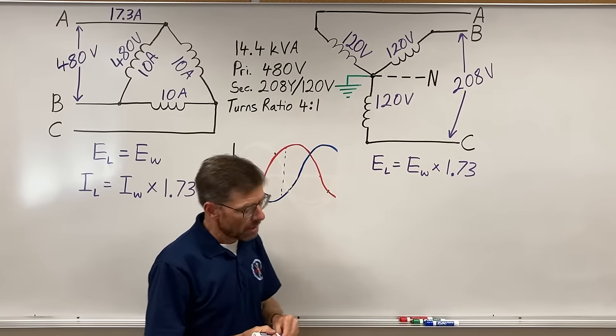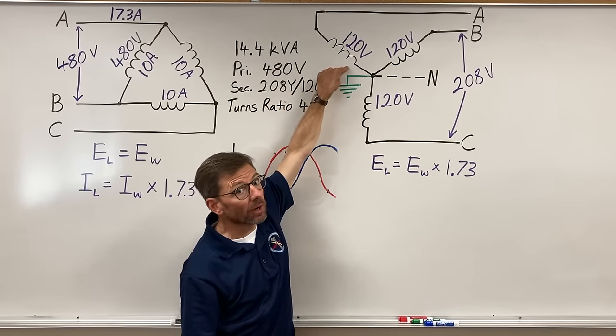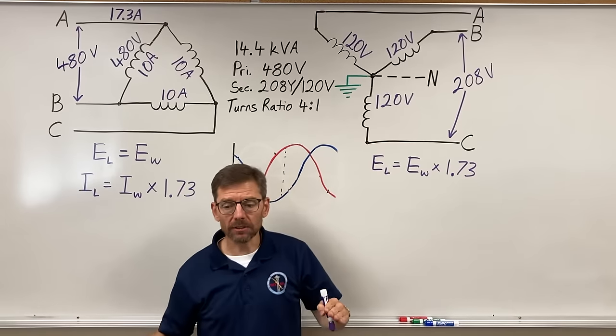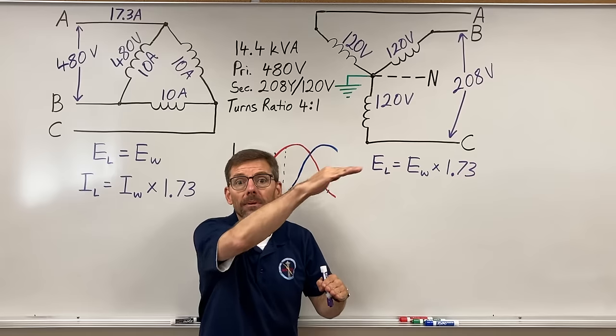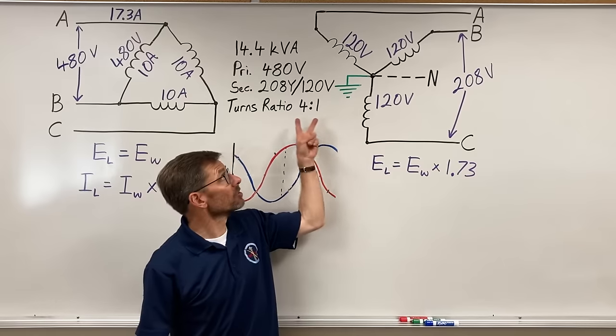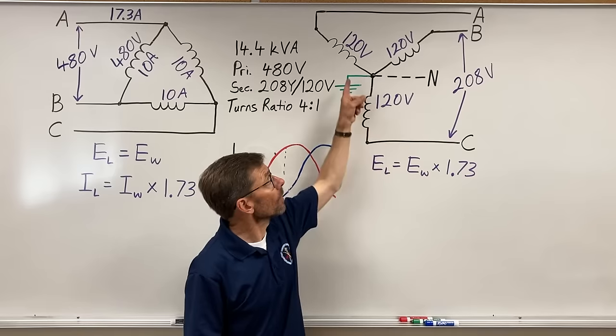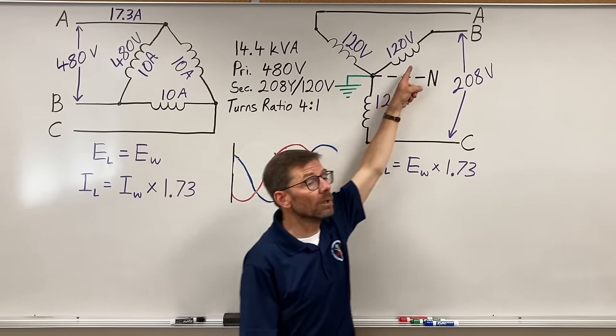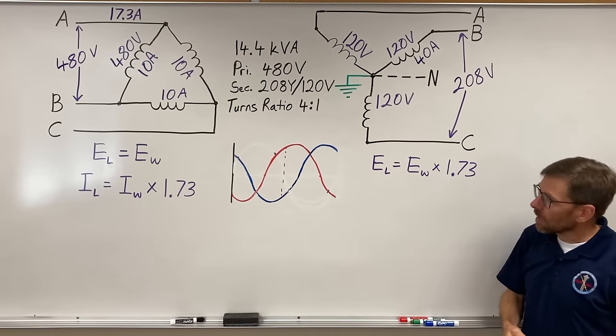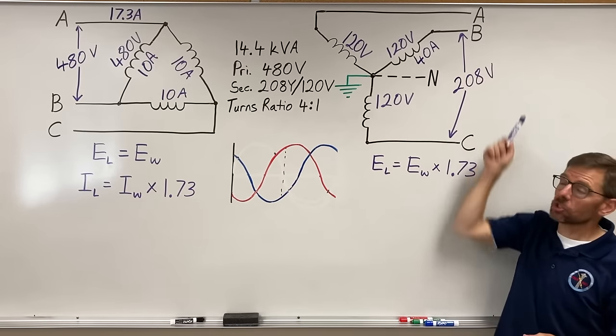Now, what's the current here? If the voltage went down by a factor of four, voltage goes down, current is inverse. That must go up by a factor of four. So 10 amps through the winding. Remember, my turns ratio is talking winding to winding, not line to line. 10 amps here will equal 40 amps through this winding. Now, what's the relationship to the winding current here and how much current goes down each line?